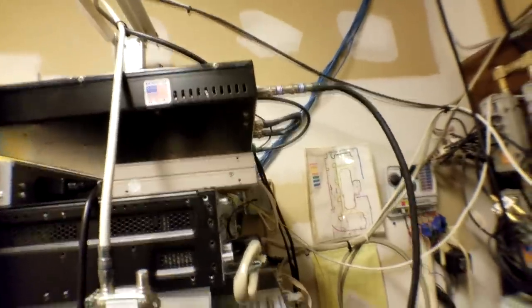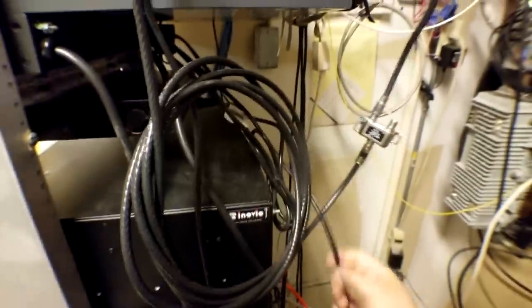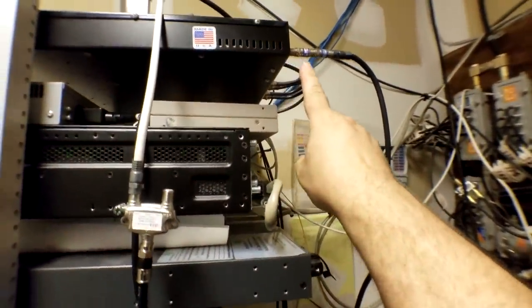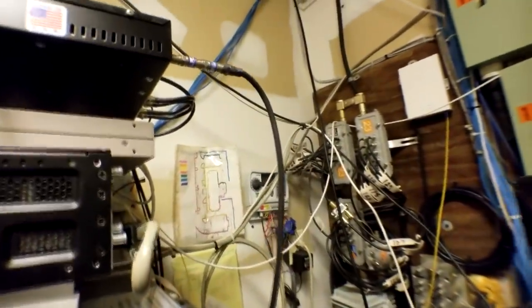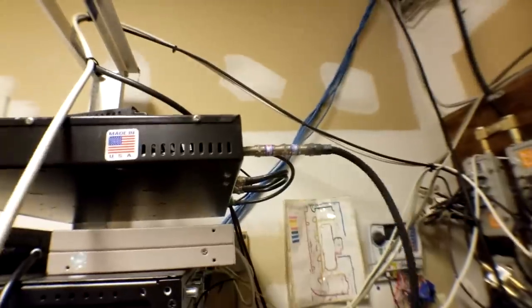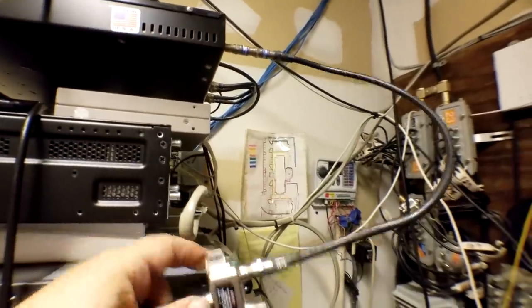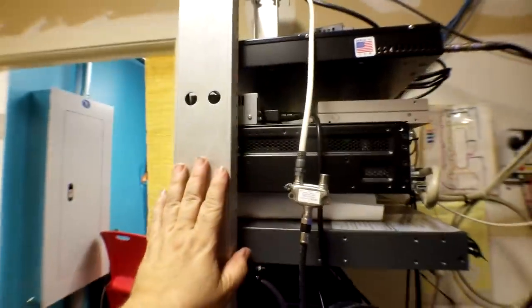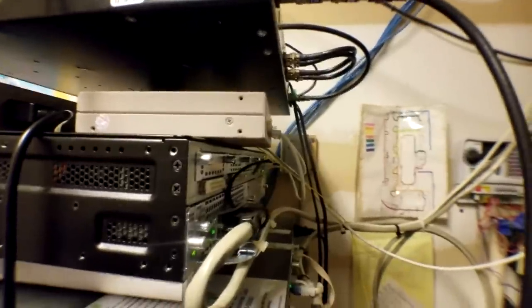Strain relief would have been a thoughtful thing to do here — you have the weight of this cable plus another cable on top of it, and this long extension with stacked attenuators to reduce signal strength because it was too hot. What's worrisome is the weight pulling on these connectors; it's so far from the rack it's going to eventually start to fail. This is where I would have considered using something to mount this line and secure it to the rack so there's no weight being pulled on that connector. These are the things you want to consider when putting these things together.